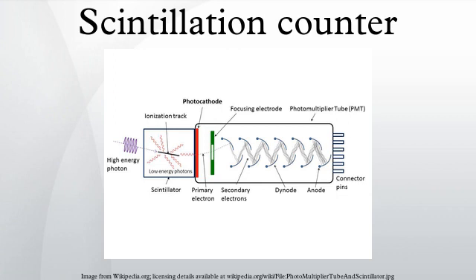The resultant scintillation energies can be discriminated so that alpha and beta counts can be measured separately with the same detector. This technique is used in both handheld and fixed monitoring equipment, and such instruments are relatively inexpensive compared with the gas proportional detector.